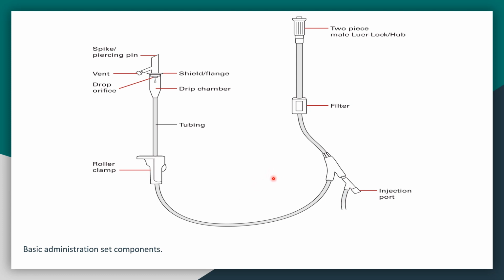So these are our basic sets. Let's start here. This is the spike. This is what goes into the bag. If you have a vent, it's right here. Then this is your drop orifice. It's what is actually dropping each drop. Then it goes into the drip chamber, down the tubing. This is the roller clamp that regulates the flow. If it's all the way down here by the wide end, it is wide open. Rolled this way, it becomes tighter and seals off this tubing.